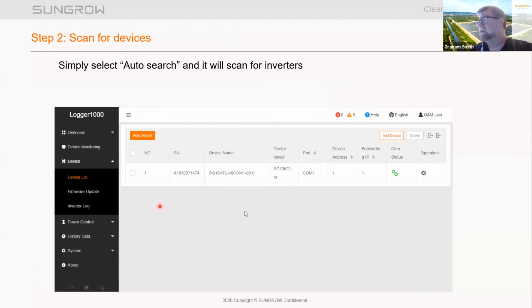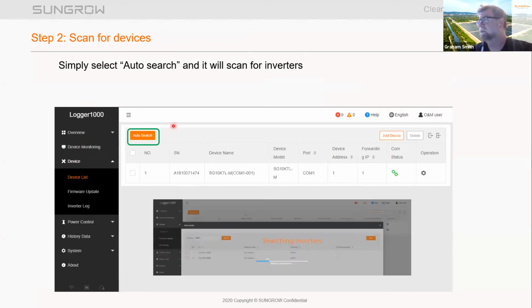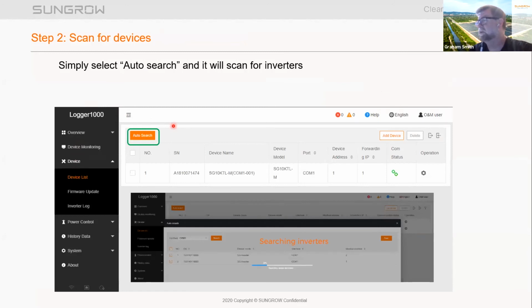Now you're going to have to scan for your devices. So you go into device list, and you hit the auto search. Now this will scan for the inverters, and you'll get this little box coming up showing that it's scanning for the inverters. Just give it a minute, 2 minutes, let it complete its scan, and once it's done that, just check that it's found all of the inverters. If there are inverters missing, check your RS485 cabling. And you'll know, because once you've said yes, you've got the inverters, you'll get this little link here.